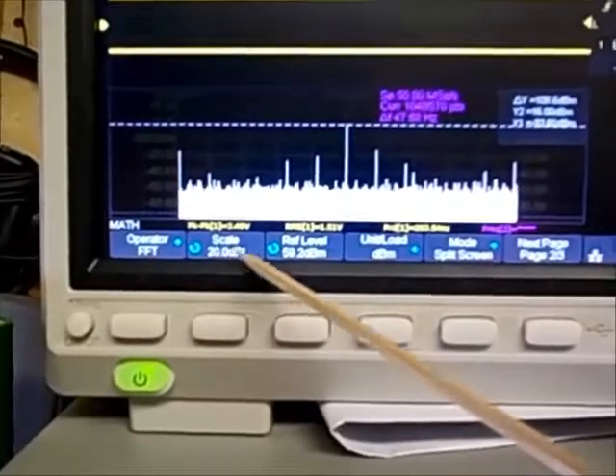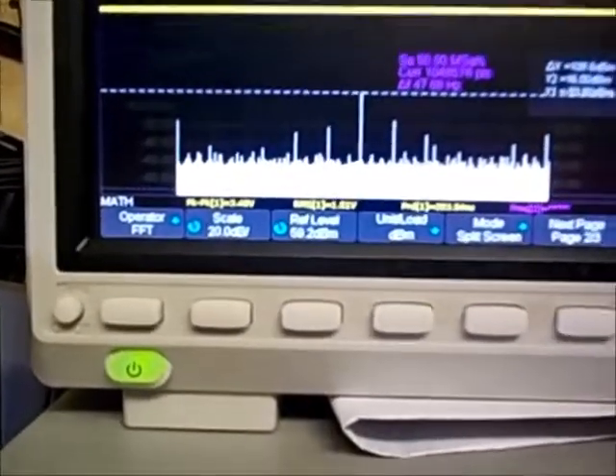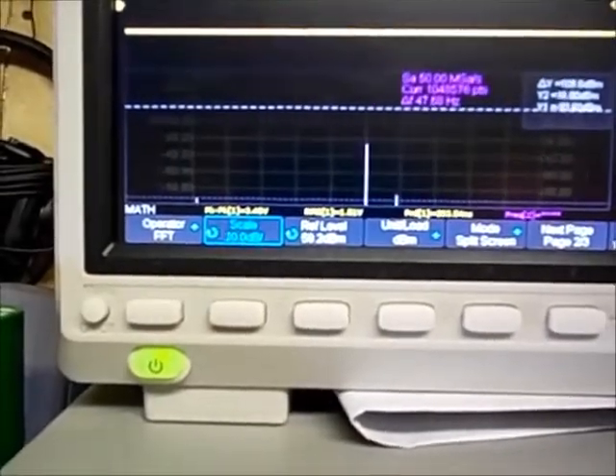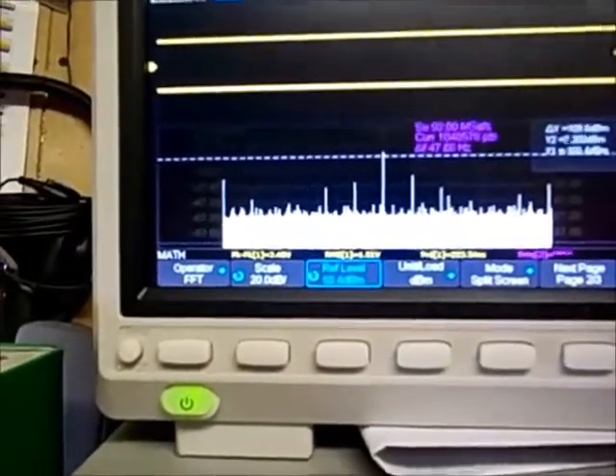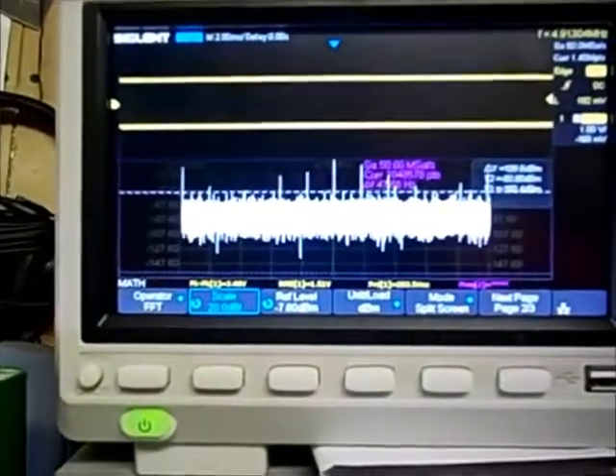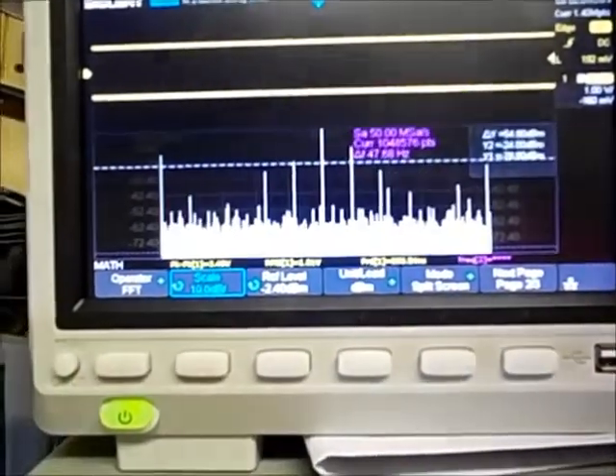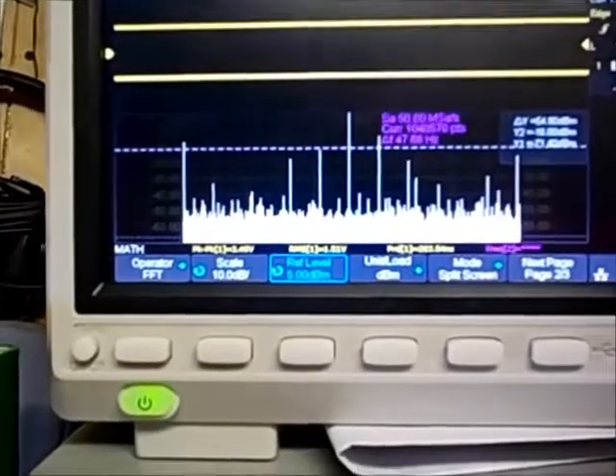You've got a scale which tells you the vertical resolution. Right now it's 20 dB per division. If you change it to 5, it disappears off the screen because it's too high resolution. The reference level shifts the display up or down. If I want better resolution at 10 dB per division, it shifts the whole display down, and I can shift the display up — but at that resolution the noise here looks very large.